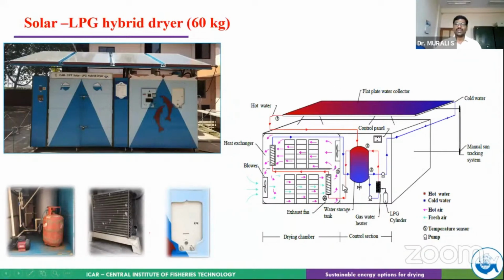That will be sent to a heat exchanger placed inside the drying chamber. You can see this heat exchanger placed inside the dryer. So the hot water will go to heat exchanger 1, then to heat exchanger 2, and then it will come back to the same tank at the bottom side. Why? Because when it goes inside the heat exchanger, it releases its heat. Upon releasing its heat, it becomes cold, so obviously it comes and connects at the bottom side.